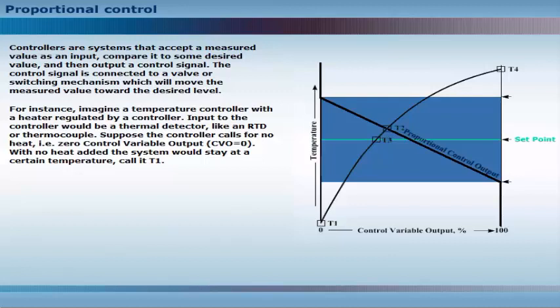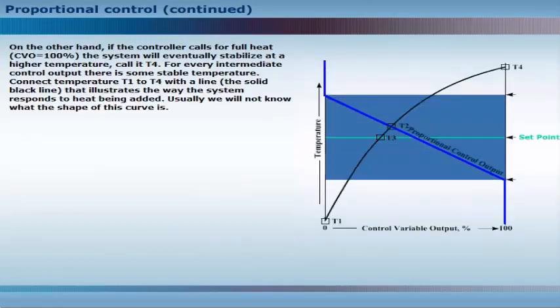Call it T1. On the other hand, if the controller calls for full heat, the system will eventually stabilize at a higher temperature. Call it T4. For every intermediate control output, there is some stable temperature. Connect temperature T1 to T4 with a line that illustrates the way the system responds to heat being added. Usually, we will not know what the shape of this curve is.